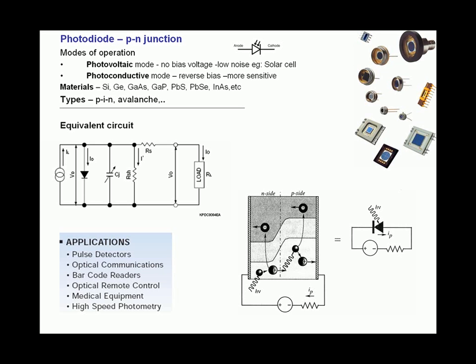Some of the more common types of photodiodes you'll encounter are the PIN and the avalanche photodiode. The PIN photodiode has an intrinsic or undoped layer between the P and the N, whereas in avalanche photodiode, which is relatively more expensive, the electrons generated knock off more electrons to create secondary electrons. As a result, there is a cascading effect or an avalanche. This is used when you need high gain, but much lower than what you get with the PMT.